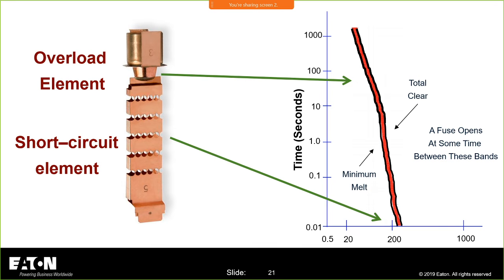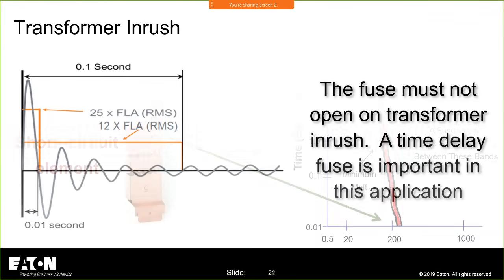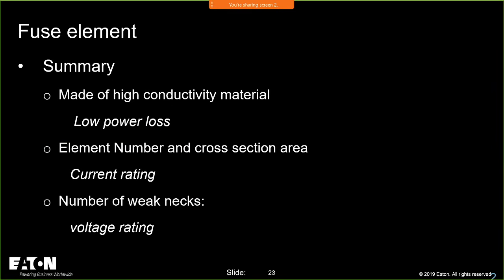So these fuses are designed with understanding where you're probably going to apply these and what some of those data points are, like for transformer inrush and for motor starting. Right. So the element itself, it's again highly conductive material. You have low power loss during normal operation. The number of the elements and the cross-sectional area gives you your current rating.